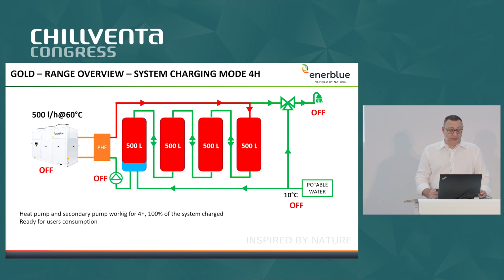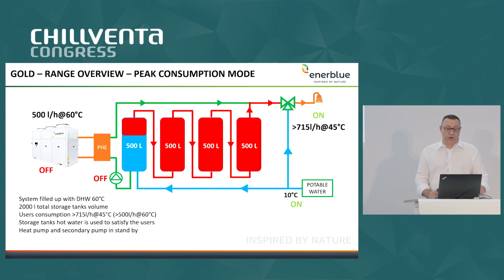When there is a request from the users, you can see there is the on near the small shower. The unit starts to use this hot water from the tanks to satisfy the users. So mixing the hot water with the city water, we can reach the tapping temperature and satisfy the users. This is the first part of the functioning, because in this case, consumption from the users is one of the peaks. So it is higher than the heat pump capacity at that moment. So we start to use the water from the tanks.